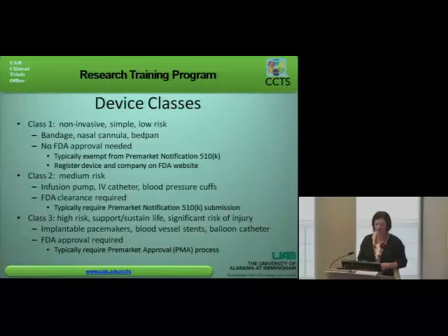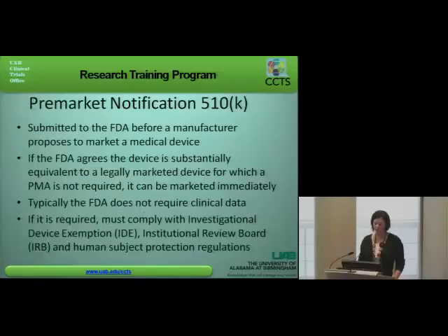Class 2 is a medium-risk device. This is something similar to an infusion pump, IV catheter, or blood pressure cuff. It does require FDA clearance, and this is typically done through the pre-market notification 510K submission process. Class 3 is a high-risk device. It's typically used to support or sustain life, and there is significant risk of injury involved. These would be implantable pacemakers, blood vessel stents, or balloon catheters. And with this type of device, FDA approval is required, and this is typically done through a pre-market approval process, or the PMA process, which I'll talk about in just a minute.